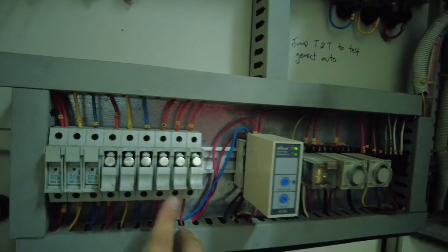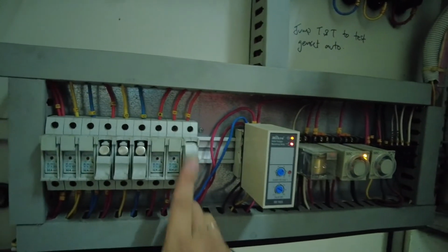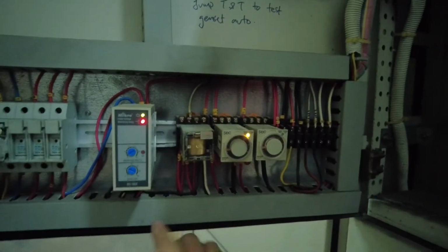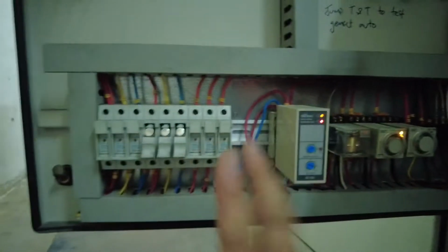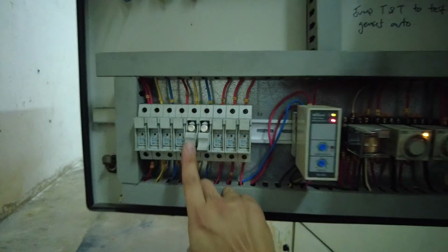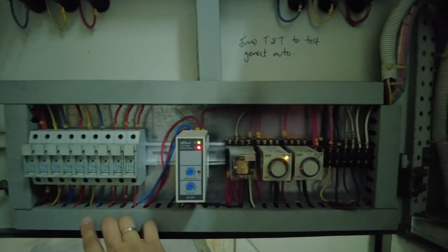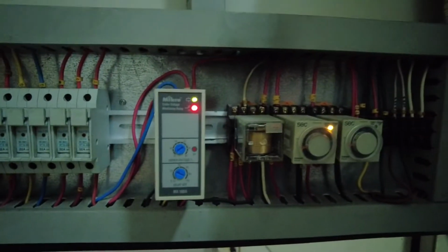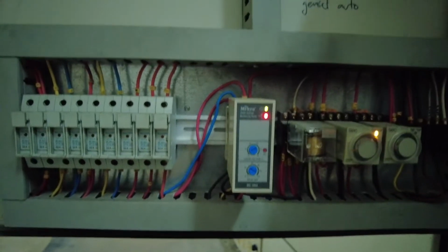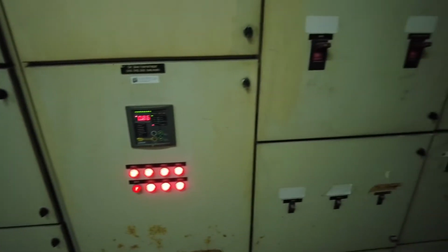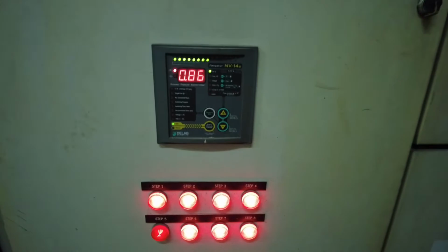Alright. And this one. Okay. Okay, now this one already operate, this one already operate. Only then, last, we put back the genset fuse. Okay. Once this one is operating, the genset will initiate the automatic stop. That means the shutdown timer will start to operate. Okay. See, the genset is still running. Okay. This power factor quite low. Need to replace the capacitor bank. Alright, later we will go to another LV room to test another genset using the same method.